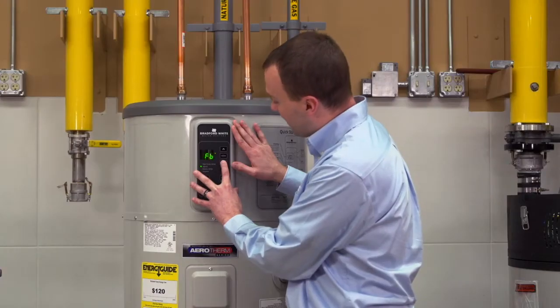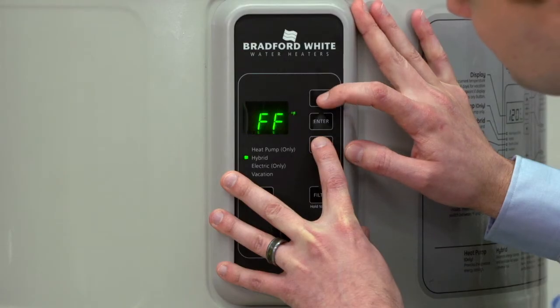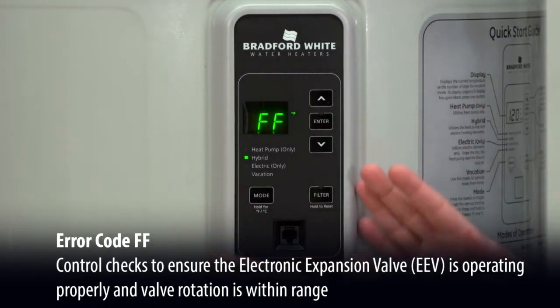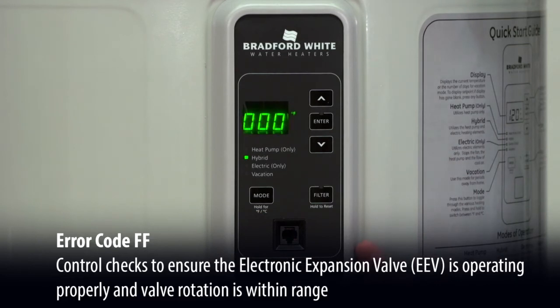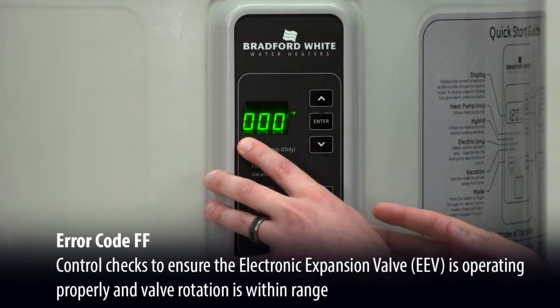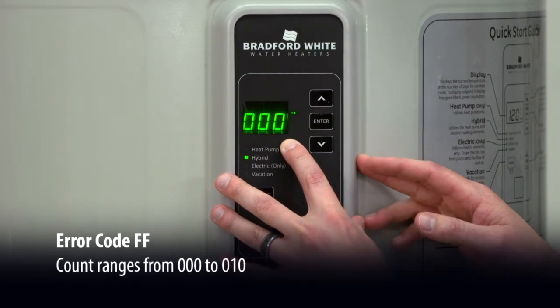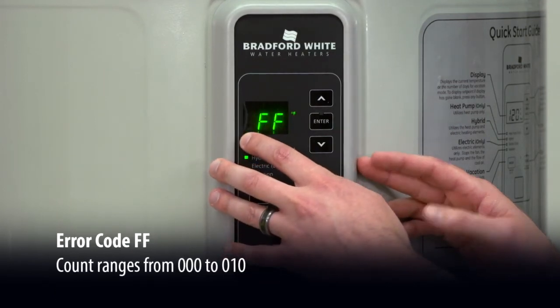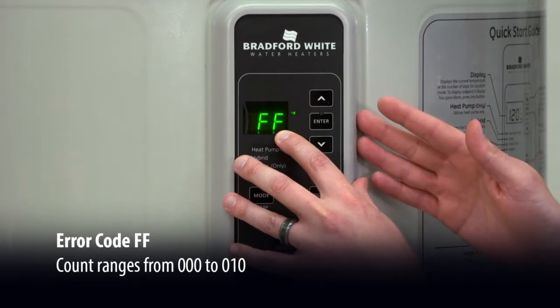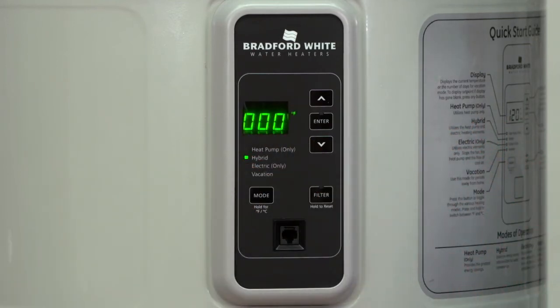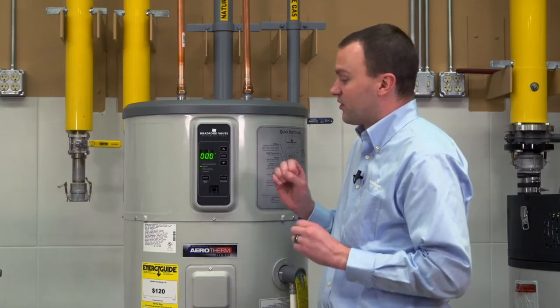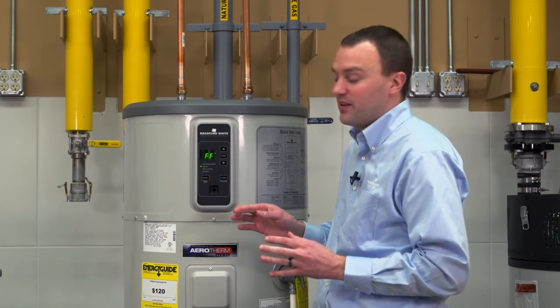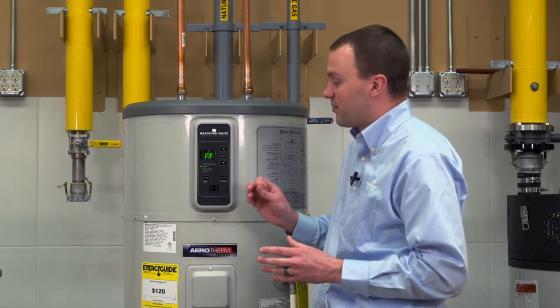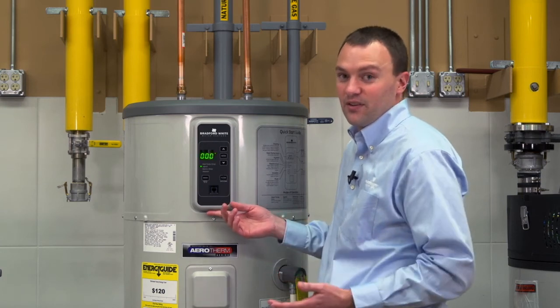So we'll go ahead and check the FF error code. FF to me is typically going to indicate an issue with the refrigeration system. As you can see, we haven't had any FF error codes on this control. If we had, we may see a number, an 8, a 9, or a 10. The control for every successful cycle will remove one fault, but for every failed cycle, will give you a new fault. Once we hit 10 faults, the control will go into a lockout and give us a permanent fault code, which will switch the unit from the refrigeration cycle to the electric cycle.